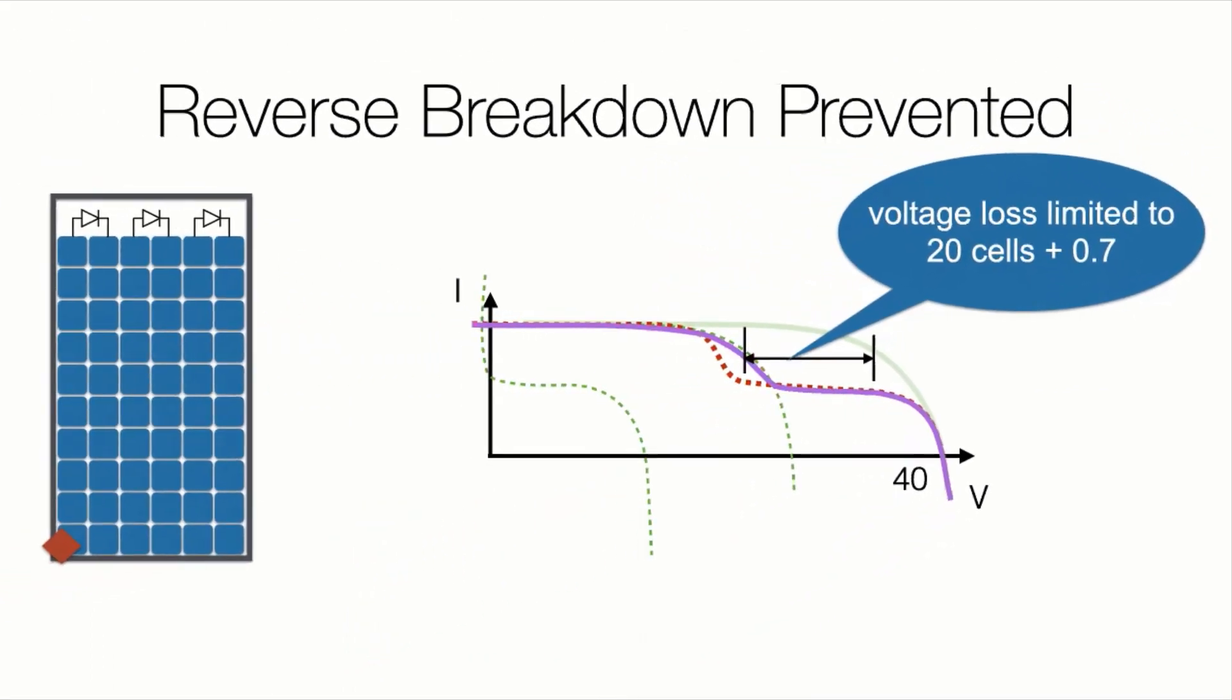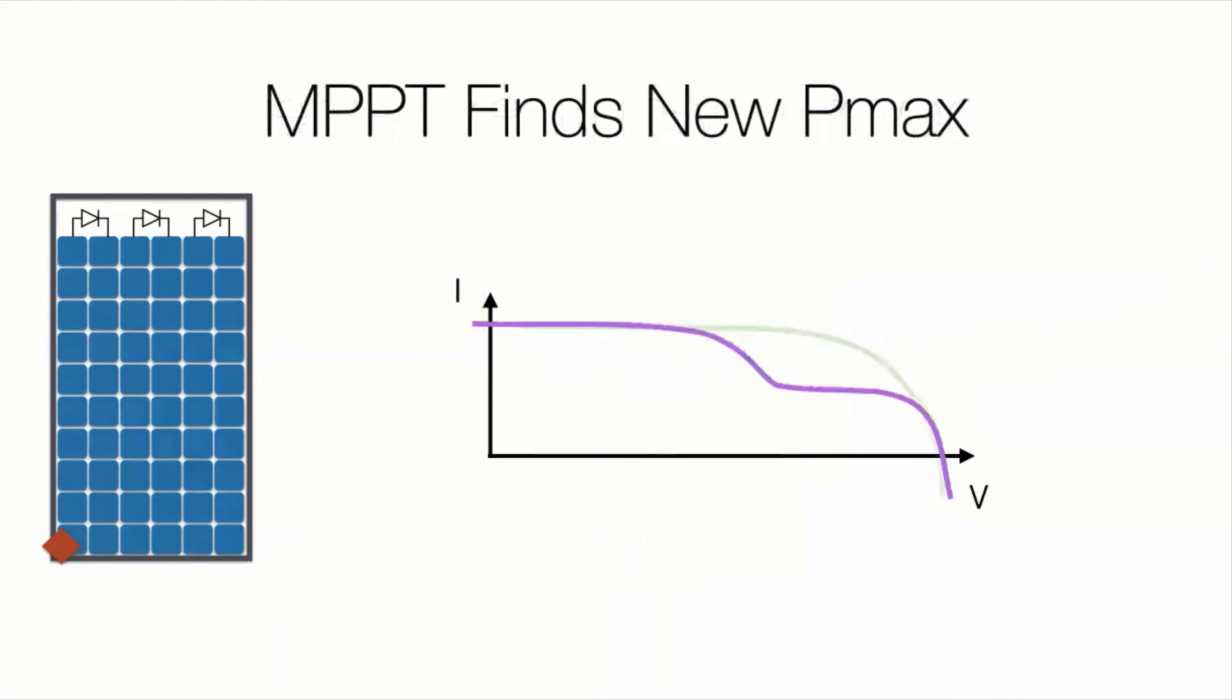So now, when you connect it to an inverter, it looks at max power operation points. And where it would have normally operated there, now it operates here. And it can operate at this high current level without reverse breakdown, because remember, it's being protected by the bypass diode.